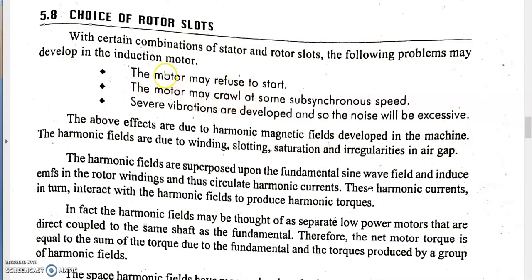In induction motor, the following problems may develop. The first one is the motor may refuse to start. The second problem, the motor may crawl at some subsynchronous speeds. And the third problem is vibration and noise may be excessively developed in the motor. So these three problems should not occur in the motor. They will occur when certain combinations of stator and rotor slots are preferred. So what combinations of stator and rotor slots should not be there, we are going to discuss now.